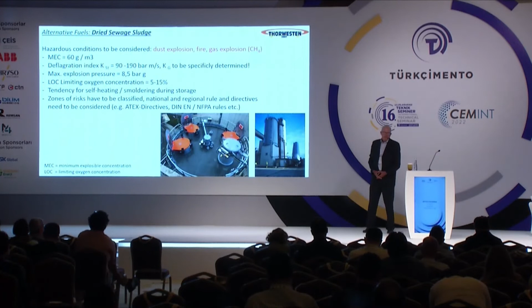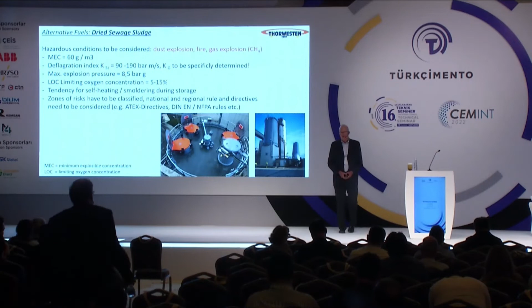Here we have some basic figures in terms of minimum explosive concentration. 60 grams per cubic meter is definitely enough to create a dust explosion. The deflagration index I just mentioned, KST, is about 90 up to 190. Maximum explosion pressure, 8.5 bar. Here is an example of what we have conducted together with our sister company, Thorwesten, a silo manufacturer. This is a silo delivered to a German cement producer for 500 cubic meters of dried sewage sludge, including the necessary explosion protection by self-reclosing explosion venting devices, dedusting filter, heat point, etc. Completely delivered by Thorwesten.